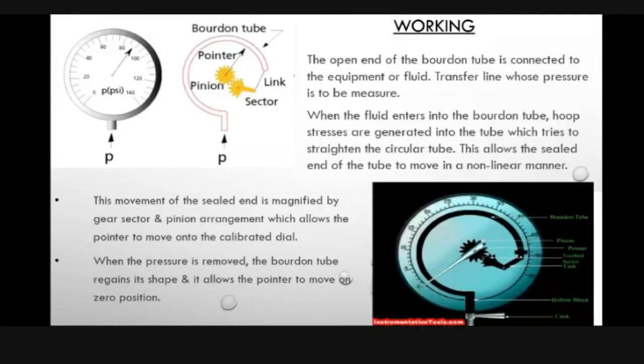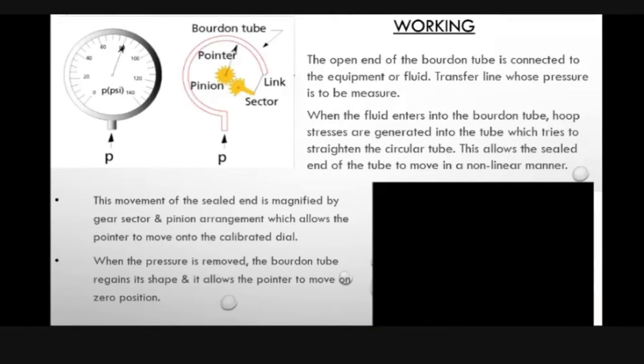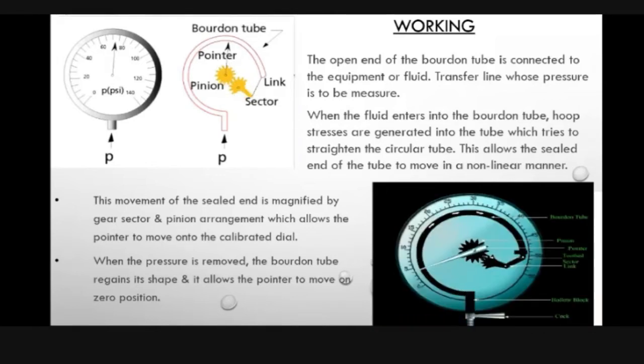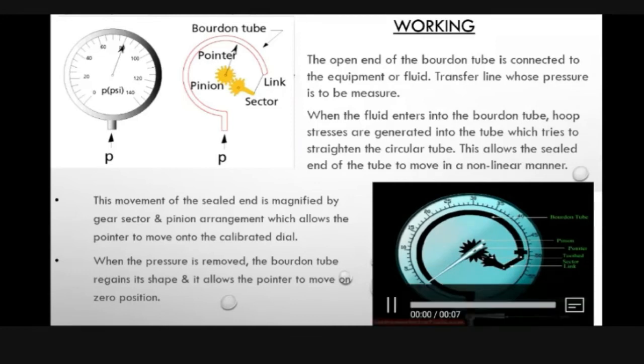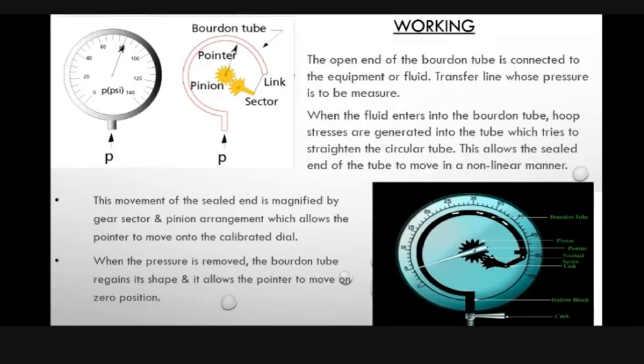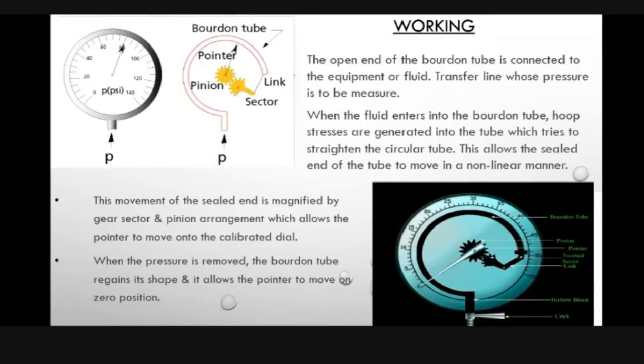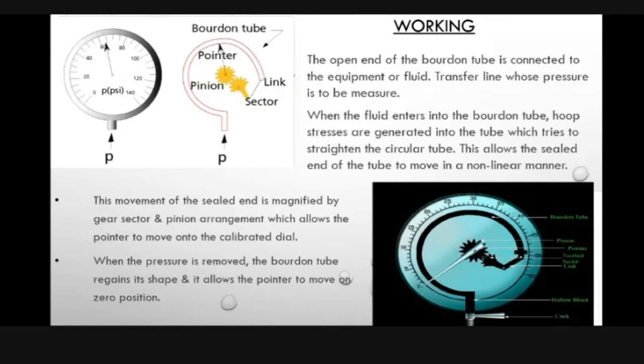Now let's see the working of the Bourdon tube pressure gauge. Before the working, let's see the working principle of the Bourdon tube pressure gauge. When an elastic transducer such as a Bourdon tube, in this case, is subjected to a pressure, it deflects, and this deflection is proportional to the applied pressure when it is calibrated. As you can see in the image, the open end of a Bourdon tube is connected to the equipment or a fluid transfer line whose pressure we have to measure.